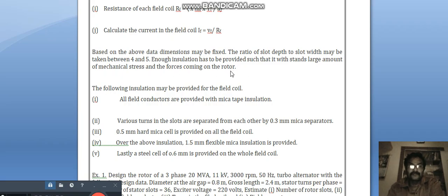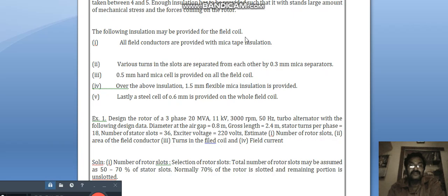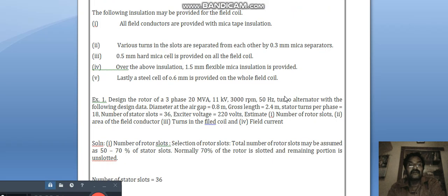Design of insulation has to be provided such that it withstands large amount of mechanical stress and force coming on the rotor. The following insulations may be provided for the field coils: All field conductors are provided with mica tape insulation. Various turns are separated by each other by 0.3 mm mica separators. 0.5 mm mica cell is provided on the field coils. Over the above insulation, 1.5 mm flexible mica insulation is provided. Lastly, steel cell of 0.6 mm is provided on the whole field coil.